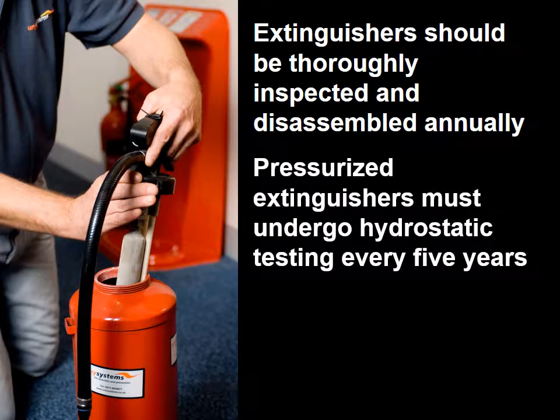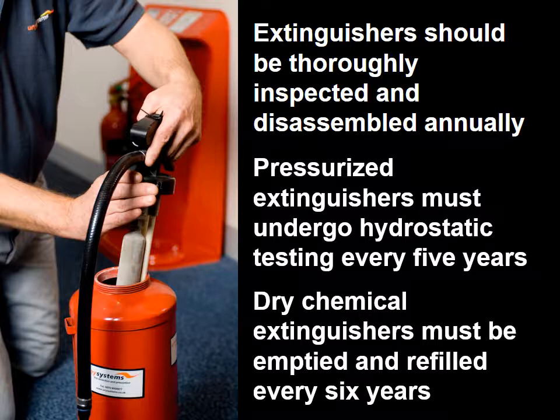Maintenance. Extinguishers should be thoroughly inspected and disassembled annually. Pressurized extinguishers must undergo hydrostatic testing every 5 years. Every 6 years, dry chemical extinguishers must be emptied and refilled.